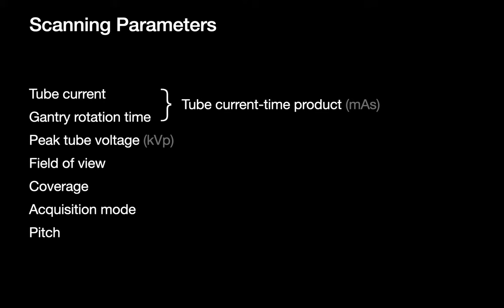There are seven scanning parameters to be familiar with: tube current, gantry rotation time, peak tube voltage (kilovoltage peak, KVP), field of view, coverage, acquisition mode, and pitch. In daily use, the first two — tube current and gantry rotation time — are often linked and referred to by their product, the tube current time product, or by its units, milliampere seconds (MAS).